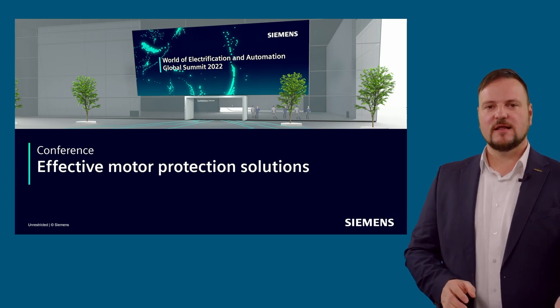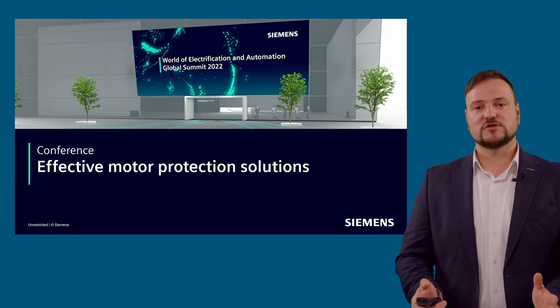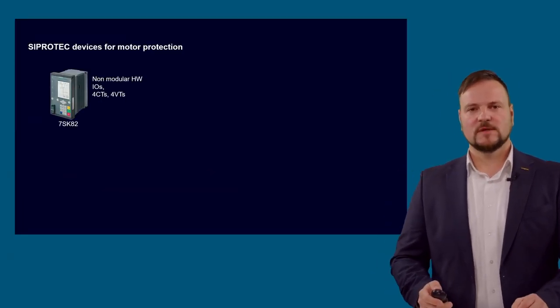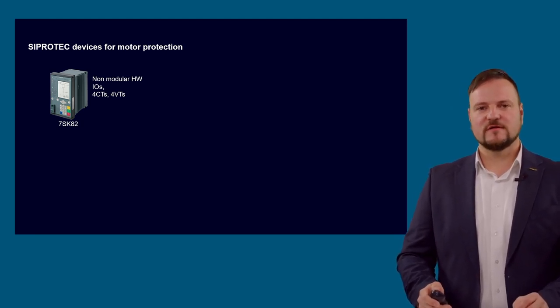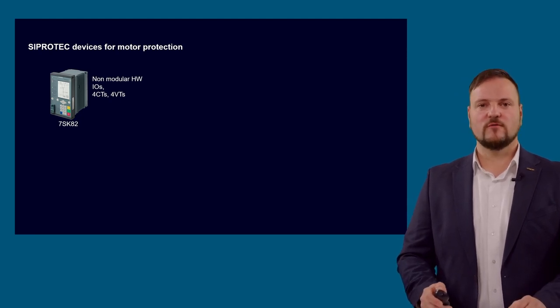Before we go into details, let me present our SIPROTEC 5 devices which provide motor protection for you. The smallest of our classical devices is the 7SK82 device which contains all necessary basic functions for protection of inductive motor or asynchronous motors. For the non-modular series, the hardware setup is limited to 4 CT sets and 4 VT sets, so that differential protection is unfortunately not possible with this device.